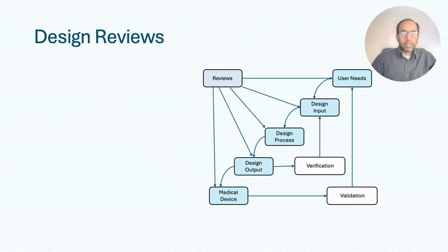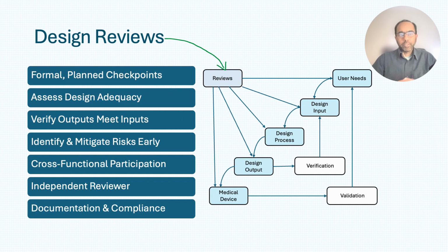Before moving any further, let's discuss design reviews. Medical device design reviews are formal, planned checkpoints conducted at critical stages of development to systematically assess the adequacy of design requirements, verify that design outputs meet design inputs, and identify potential risks or issues before they become costly.